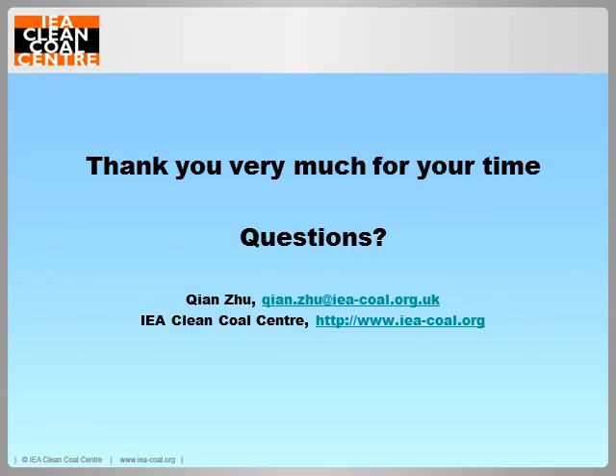Another question has come in. Qian, you showed the emission levels of a CFBC boiler, and they're not that impressive. Much lower emissions can be achieved today by a PC plant. Is this likely to limit applicability of CFBCs as legislation tightens in the future? The CFBC boiler at the moment, without any addition of flue gas treatment systems, can meet the emission requirement in most regions. However, you can use the post-combustion systems, such as the dry scrubbers or the SNCR system, to further reduce its emissions.